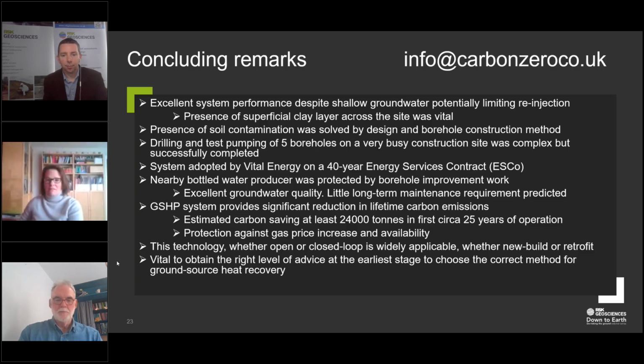Yes, so we've mentioned that ground source has the great advantage of being able to heat and cool. You don't need additional plant. A traditional plant room would have boilers and chillers. A correctly specified heat pump will heat and cool either at the same time or in different seasons. So the plant room will be designed so that if a building has a gymnasium and a server room as well as rooms which require heating, then that heating and cooling will be managed internally, and it's the net heating or cooling which is then taken from or put to the ground.